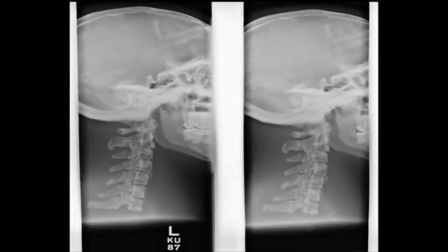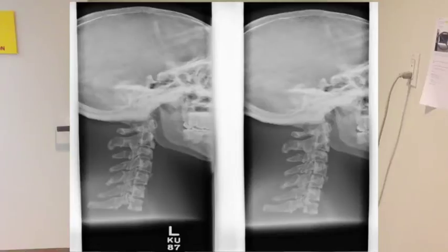Although both images are supposed to look identical, the original image, which is the one on the left, has a better resolution because of the small focal spot size. A small focal spot size is best for the image because it provides better recorded detail, but not the best for the equipment if being overused.